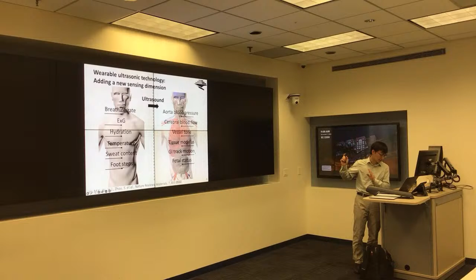So what you're looking at here is the schematic of this wearable ultrasound patch that we published about 6 years ago. In this case, there are 100 transducers, a 10 by 10 array. And each one of the transducers is individually connected, addressed to transmit and receive ultrasound. And on the right here is the exploded view of a single transducer. So it's multi-layered to maximize the performance of each transducer, so that you can transmit more ultrasound into the human body and receive the highest signal-to-noise ratio of these echoes from the human body.